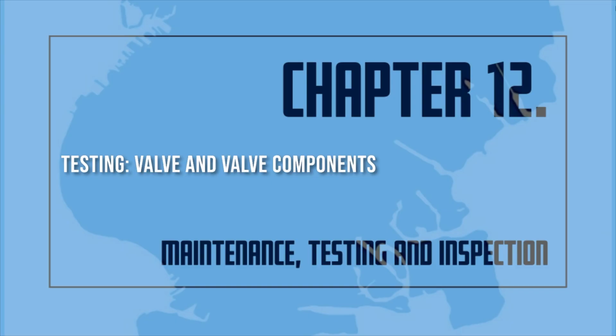Post indicator and outside screw and yoke valves shall be backed a 1/4 turn from the fully open position to prevent jamming. Valve supervisory switches shall be tested semi-annually. A distinctive signal shall indicate movement from the valve's normal position during either the first 2 revolutions of a hand wheel or when the stem of the valve has moved no more than 1/5 of the distance from its normal position.